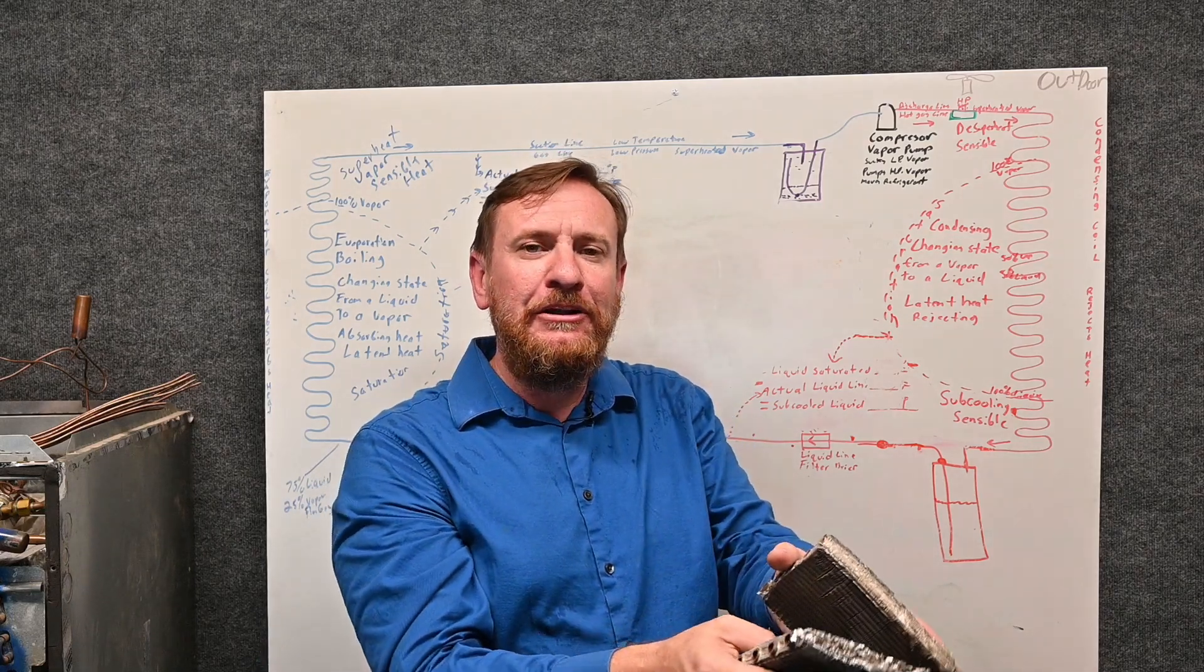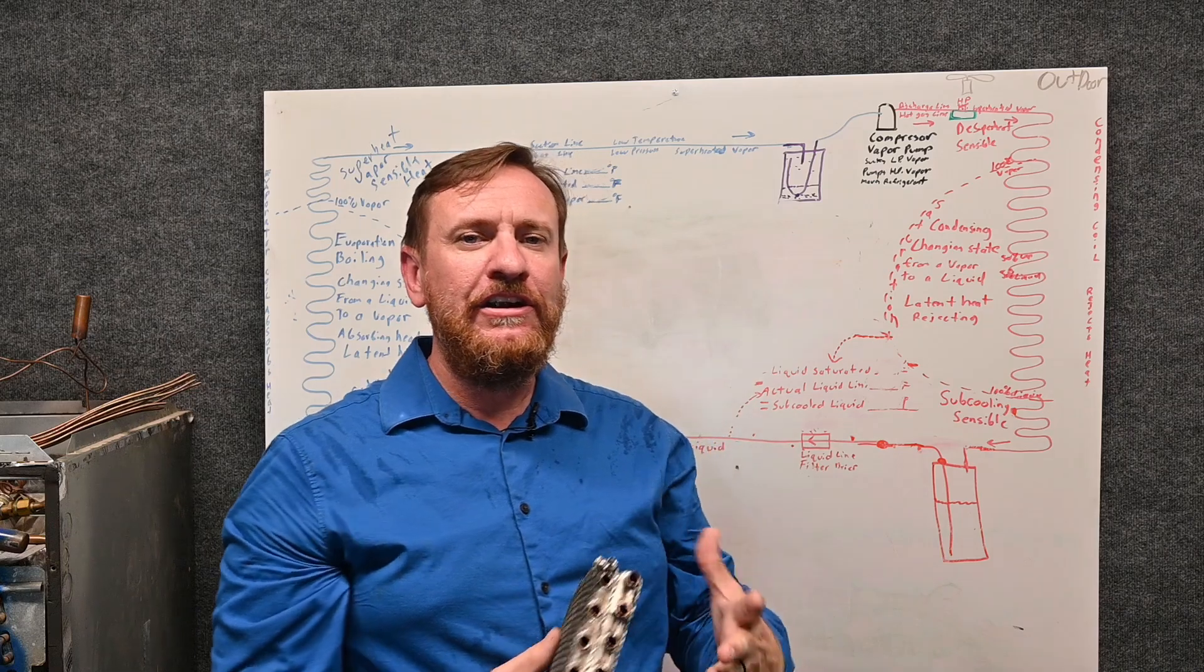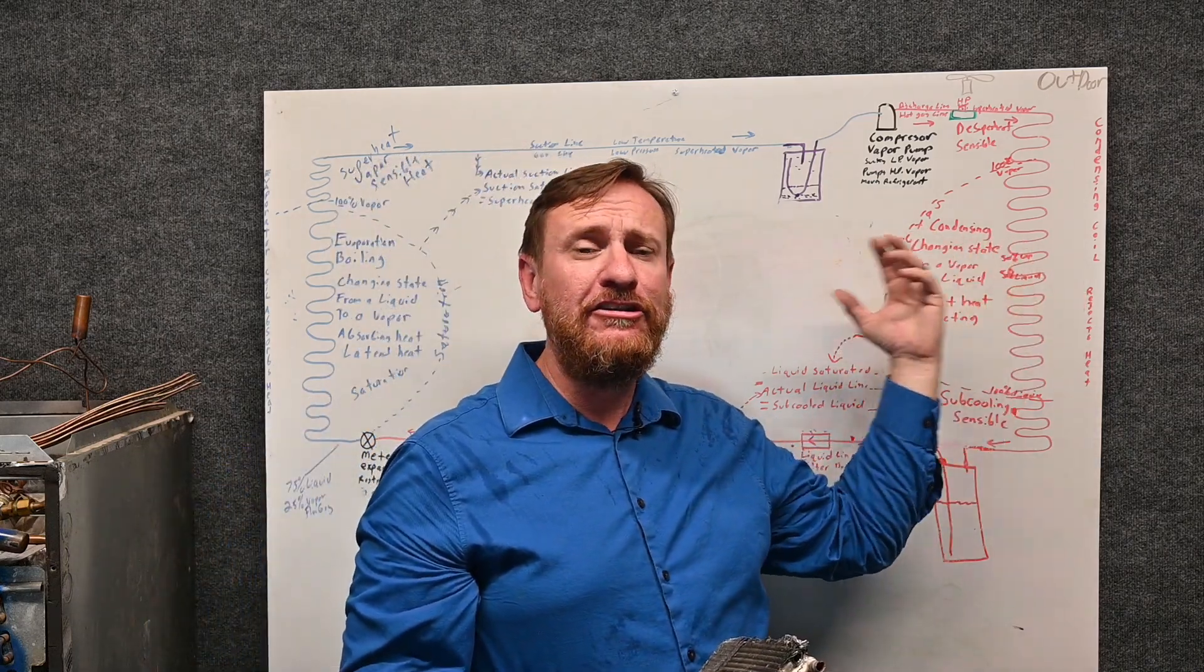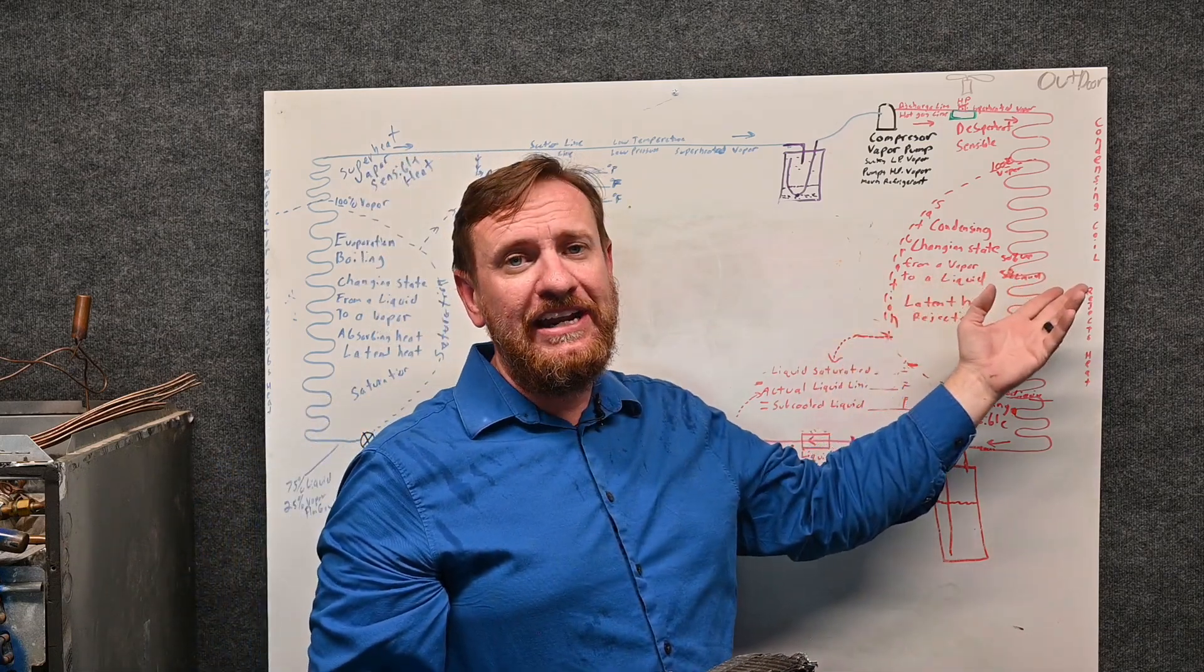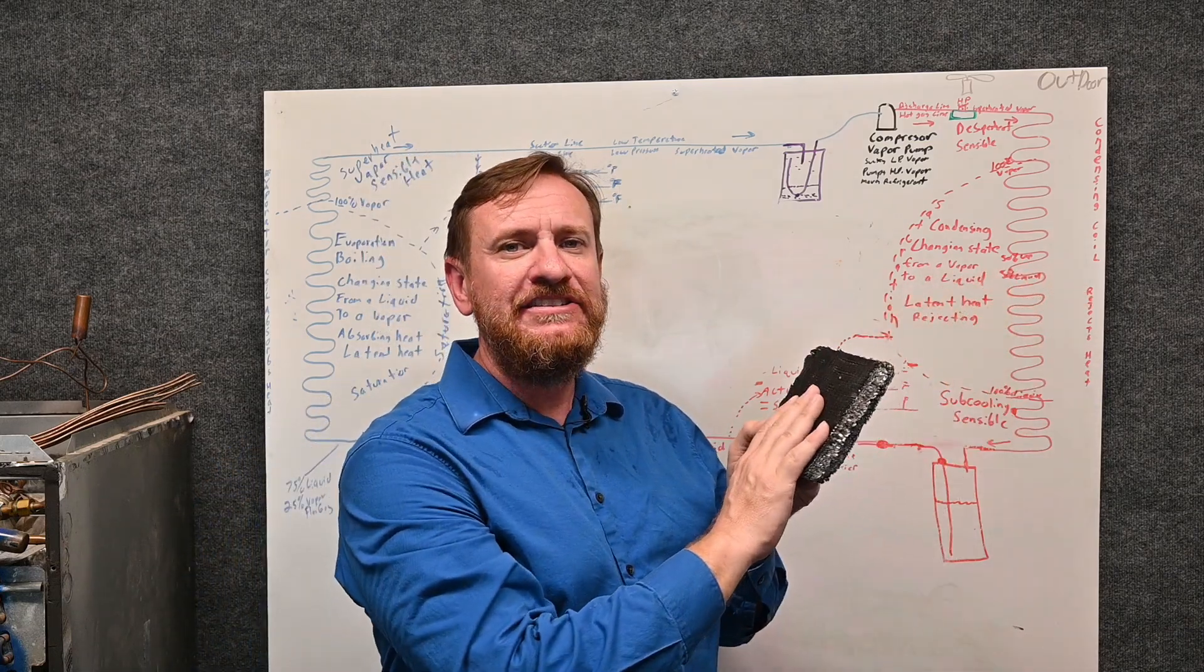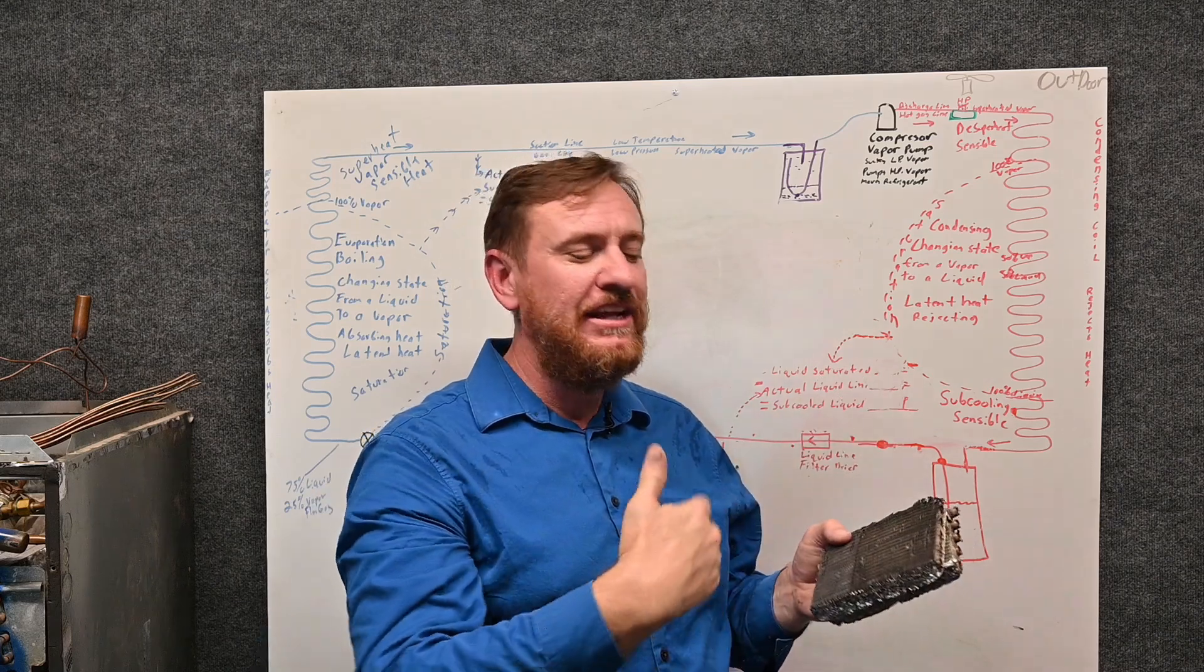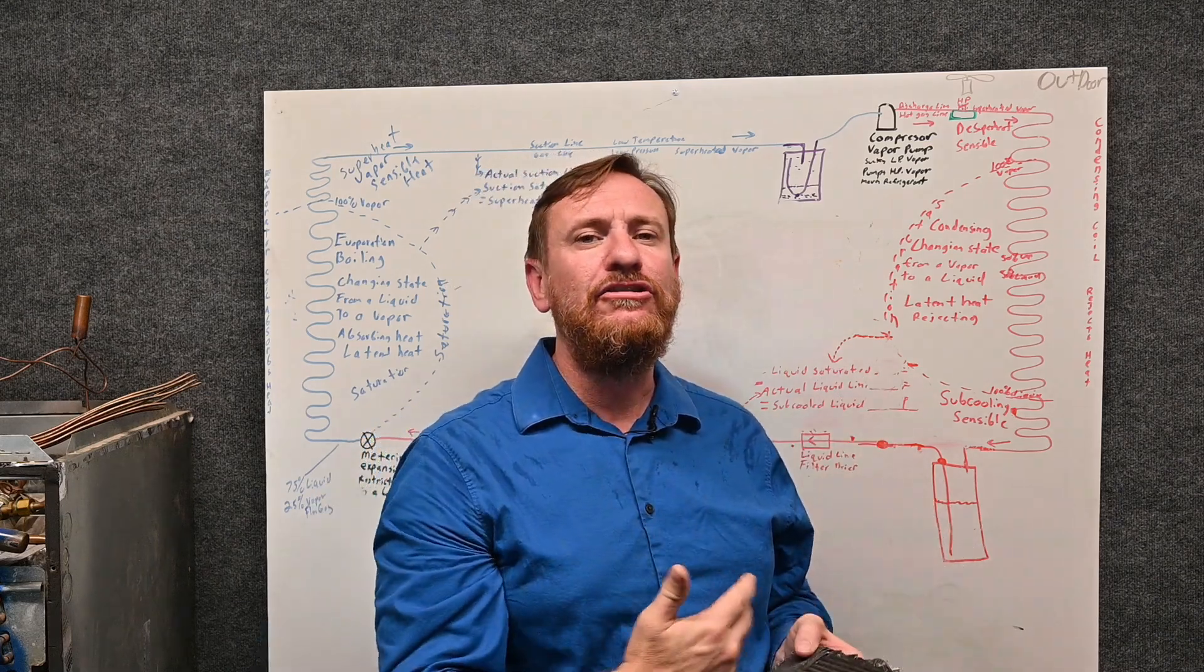That dirt can build up in between there, and that dirt is going to cause a problem with our second law of thermodynamics—it's going to slow down our heat transfer. It's going to do that in two different ways. One, it's going to slow down airflow. Number two, the dirt acts as an insulation, and that insulation, the material type, is going to slow heat transfer. So two things we want to be careful of.